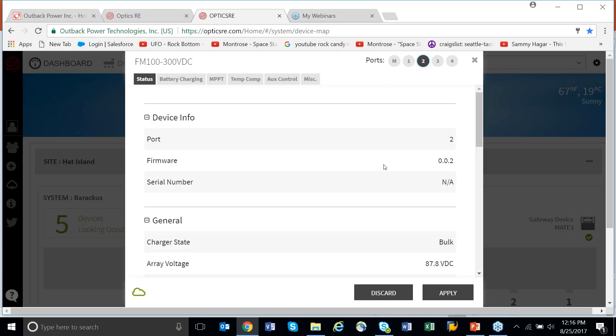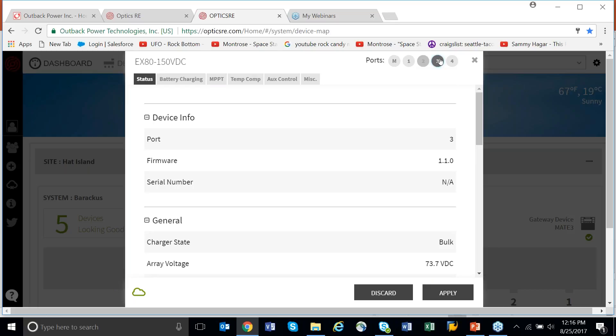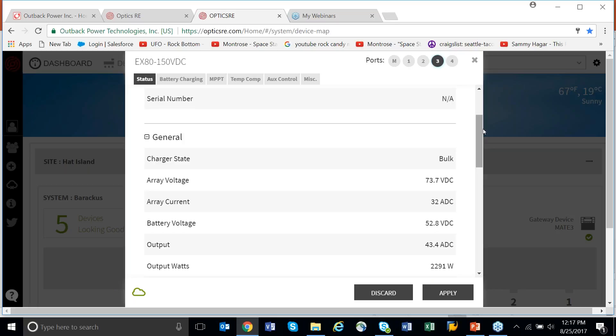Let's go look at the charge controllers — pretty much the same thing. It tells me right now the charger state is bulk, the array voltage, the array current, battery voltage is 53V, and the output current is 46.6 amps — that's the FM 100. Let's go look at the other one: 46.6 versus 43.4 amps. The FM 100 seems to harvest slightly better than the Extreme, which is cool because it's a new charge controller — hopefully seeing that is good news.